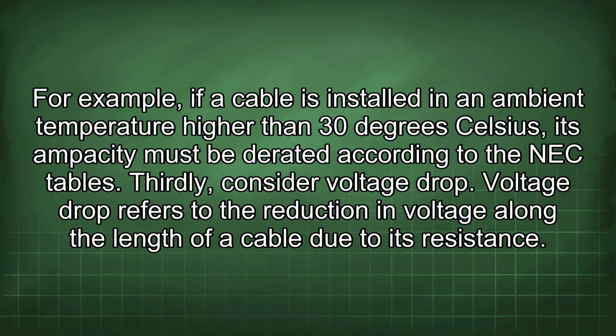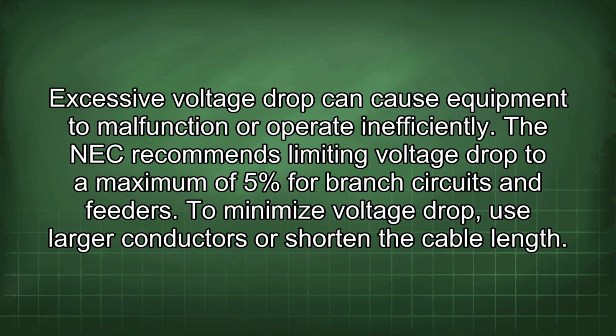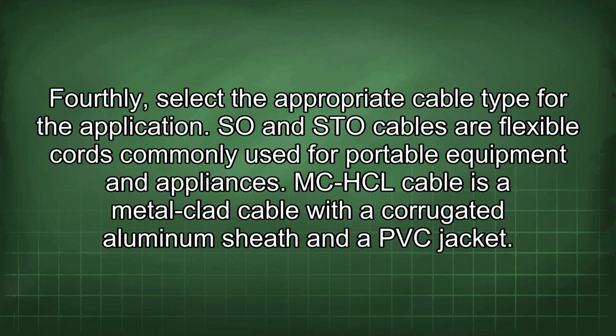Thirdly, consider voltage drop. Voltage drop refers to the reduction in voltage along the length of a cable due to its resistance. Excessive voltage drop can cause equipment to malfunction or operate inefficiently. The NEC recommends limiting voltage drop to a maximum of 5% for branch circuits and feeders. To minimize voltage drop, use larger conductors or shorten the cable length. Fourthly, select the appropriate cable type for the application. SO and STO cables are flexible cords commonly used for portable equipment and appliances.